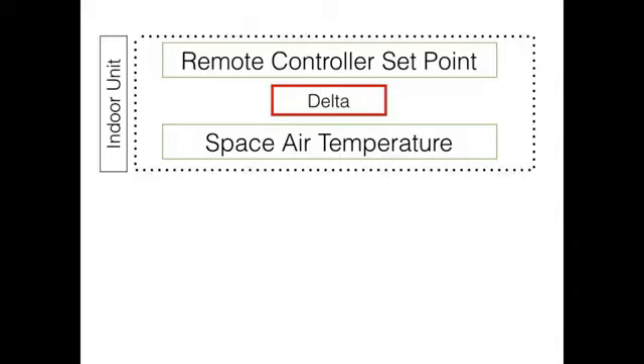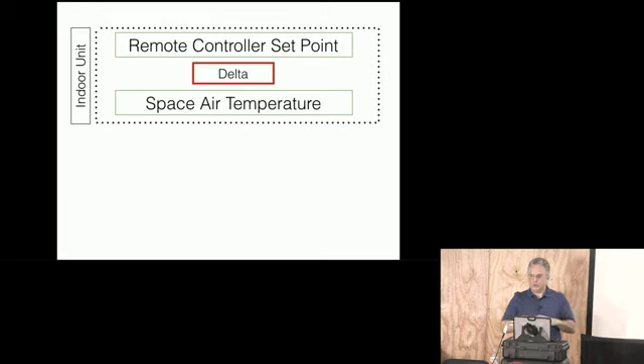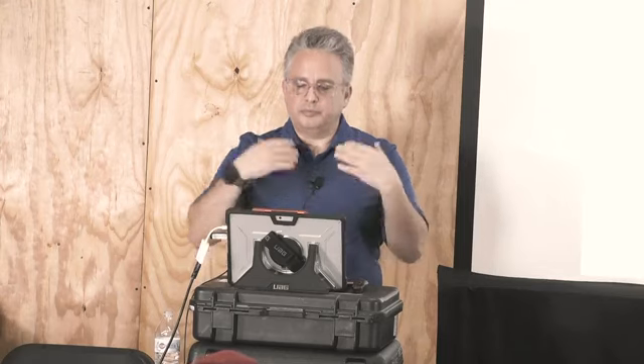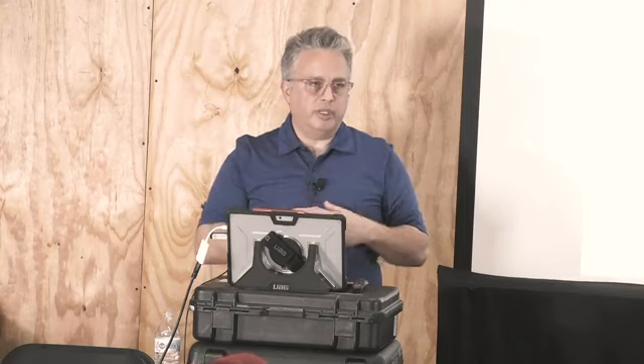So how do they work? It's called a block diagram, typically used for designing controls. So you have the indoor unit, and you have the remote controller set point. So it's not a thermostat, it's a remote controller. A remote controller does much, much more than a thermostat. A thermostat is a 24-volt on-off device, typically. And a remote controller can control vanes, can report error messages, error codes. It does a lot more than just a typical thermostat. But now that we understand what the difference is, we can call it thermostat. That's fine.